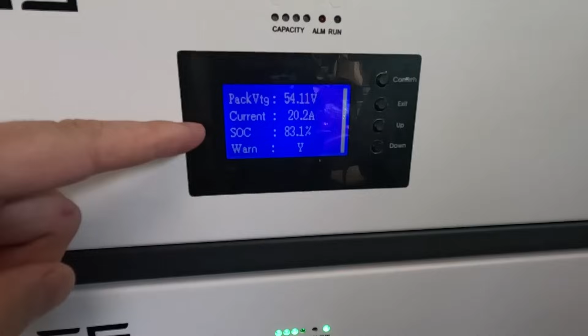If I log into this battery, you can see the current is over 23, so it's on warning now and reports only 10 amps as the CCL. But the alarm protect info down here doesn't show anything about an alarm - over ambient temperature, charge current alarm - there it is, and it's active now.